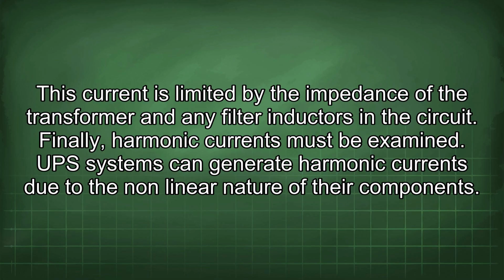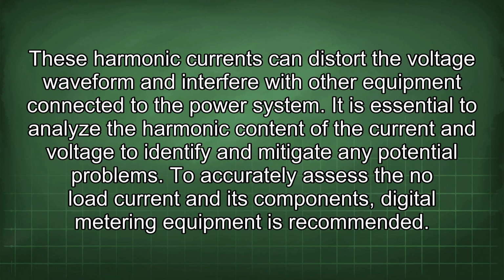UPS systems can generate harmonic currents due to the nonlinear nature of their components. These harmonic currents can distort the voltage waveform and interfere with other equipment connected to the power system. It is essential to analyze the harmonic content of the current and voltage to identify and mitigate any potential problems.